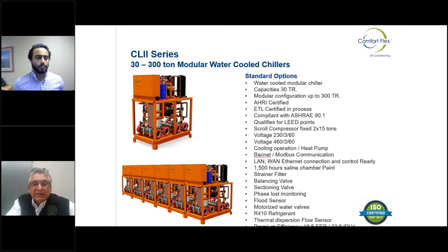There we go. Here's an example of the modular approach with 30 ton modules, two fixed scroll compressors, up to 300 ton. Again, also available either with heat recovery or as a heat pump, and also simultaneous heating and cooling. What's unique about this product is they will actually ship it with valves already assembled on the condenser water and chilled water side for variable water flow, and also for variable primary flow on the chilled water side, to control the amount of water flow through each module as the system pressure increases or decreases.